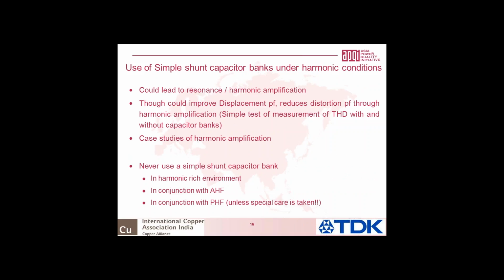because it's not now. Almost 20 years I've come across n number of cases, you know, in double-digit numbers, where customers have got a power factor improvement or a reduction in harmonic distortion by just disconnecting capacitor banks. I can go on and on. It's at least 2 cases a month I come across where, of course, me and my colleagues, we get job satisfaction and pay by selling capacitors, but I could solve the problem by disconnecting capacitors.